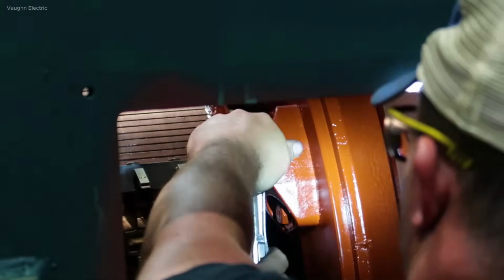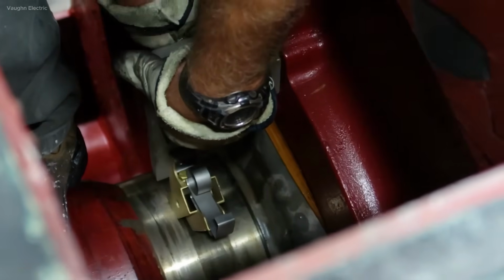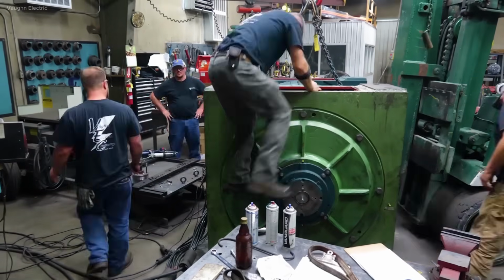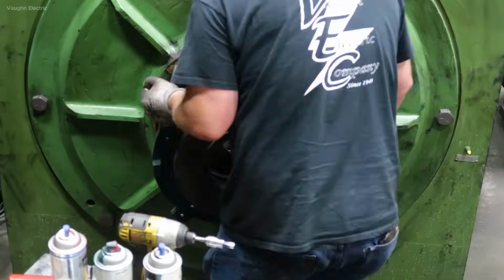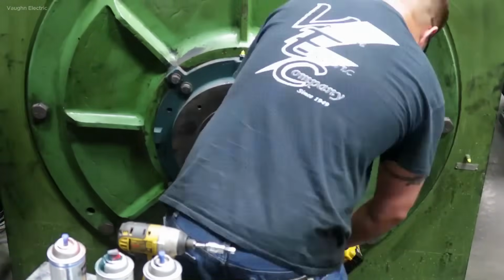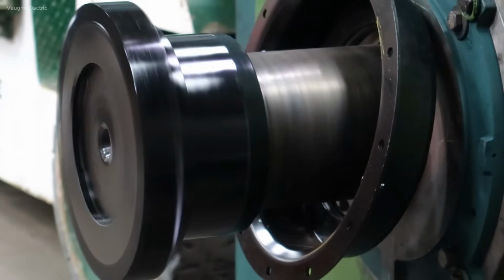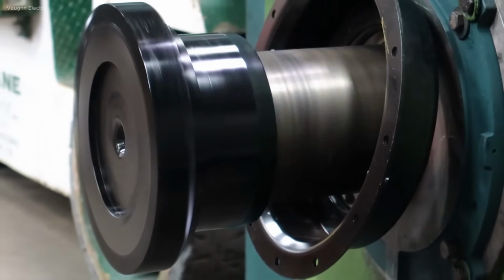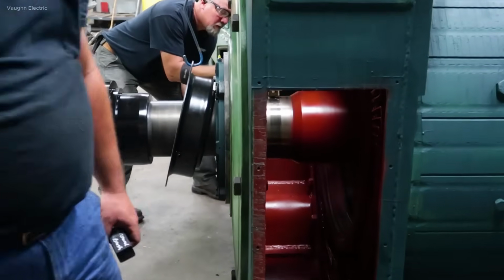Once reassembled, the motor undergoes electrical testing, including surge, insulation resistance, and high voltage withstand tests. If required, it is connected to a dynamometer for full load performance validation. After passing all tests, the motor is painted, labeled.